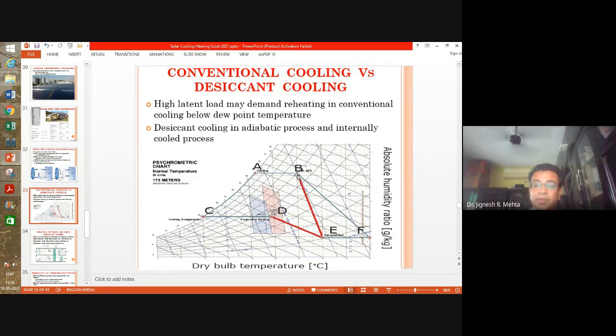But then if you are able to provide cooling, which is more possible in liquid desiccant based cooling systems, you may limit the temperature rise of the air when it passes through the dehumidifier. And this is your outlet state, where the humidity ratio is quite low and you're able to cater to the latent load of the space. And if this temperature is too high, then you might go for evaporative cooling and then put it in the space. So this is the process of dehumidification shown with the help of desiccant systems.